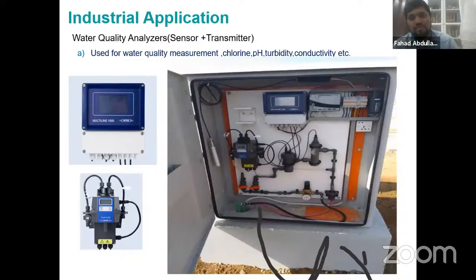This enclosure shows the complete system. It has the RTU for remote transmission, sending data through a SIM card via GPRS, 3G, or nowadays 4G and 5G communication. So you don't have to go and check the reading on site - though you can do that also, there is a local display, but remotely you will have this information in a control room. There will automatically be a record of data, and automatic reports will be generated by the SCADA software.